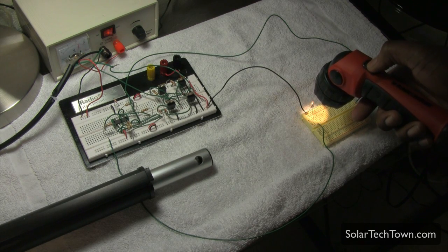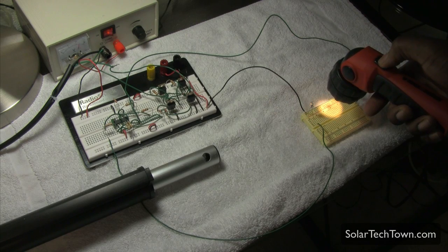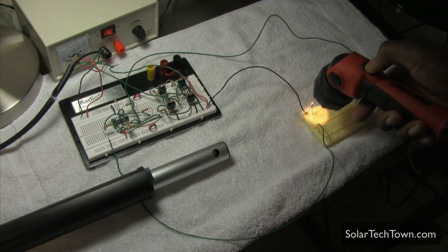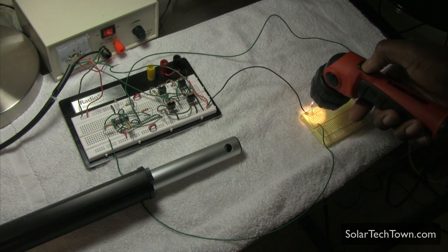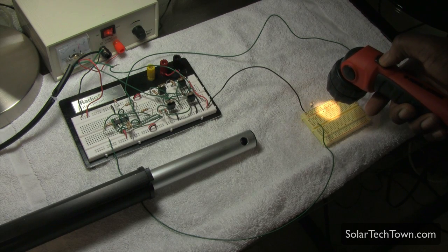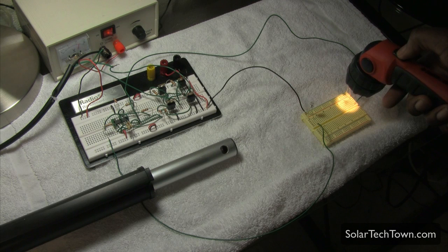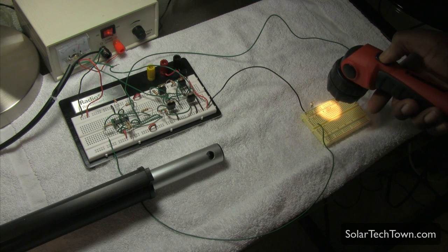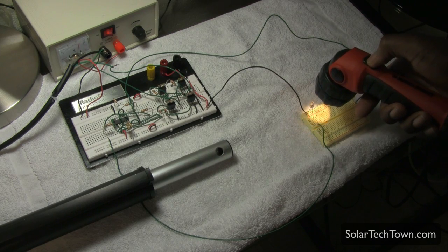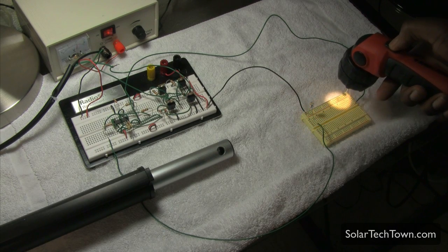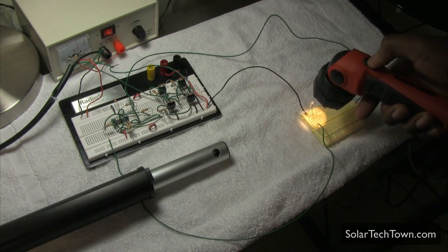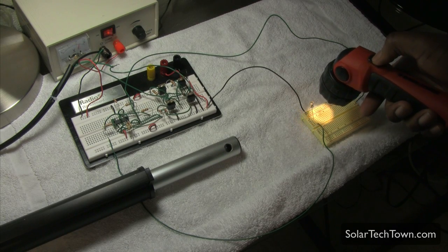So again, depending on how you built your solar tracker would determine which direction this is actually turning it. But as you can see, going here to the left is actually pulling the stroke out. Here in the middle it stops it. Now I'm going over here to the right, it's pulling it in. So these are just basic tests that I ran, and I'm just trying to show you that it does work. But again, the feature that I mentioned earlier about it returning back to the starting position at night is something that you probably want to add in.